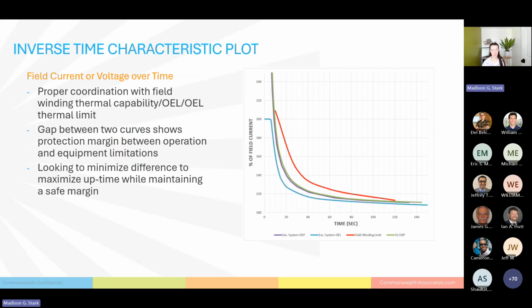Another option for coordination that you can see is an inverse time characteristic plot. For current specifically, they're also called a TCC, or a time current curve. And what this does is it allows you to coordinate your limiters specifically with the thermal limits of your field windings. So what we're looking for here is coordination moving from your corner over here outwards. And this is how you check your coordination. So again, we want to hit that limiter first. We always want to hit the limiter first. So as we move out, the first thing we hit is this limiter.